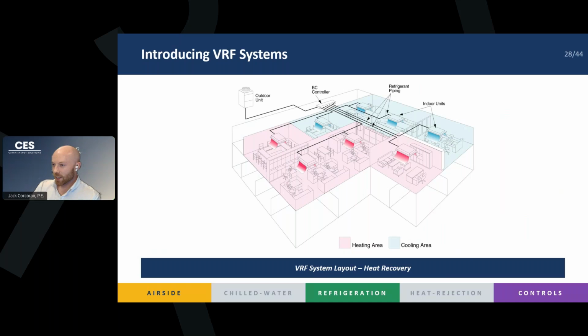And this diagram shows the heat recovery, right? And this is actually the most powerful layout that we can use in VRF systems. It allows you to have individual zone control. If you want to feed a whole office space, you're going to have dozens of offices. All of them are going to have various loads. Maybe one of them is on the shady side of the building and the other one's on the hot, sunny side of the building. You're going to want to be able to cool those sunny zones, and you're going to want to be able to heat potentially those shady zones.